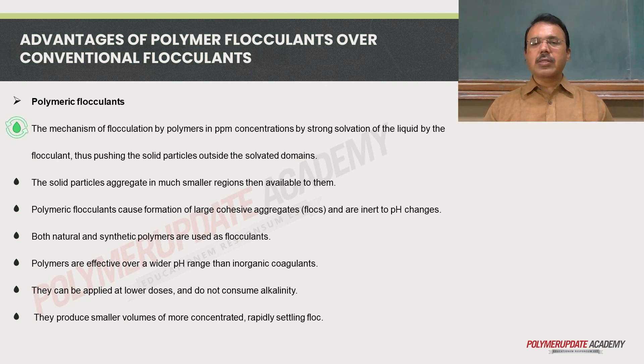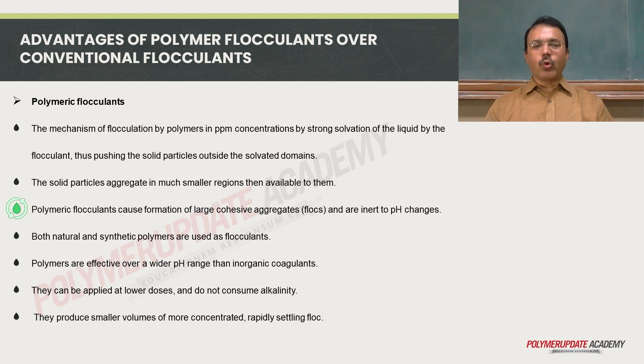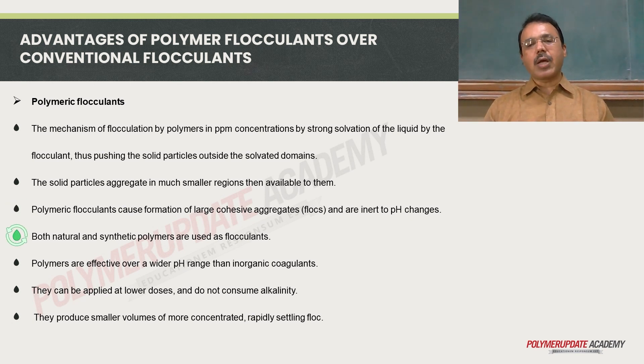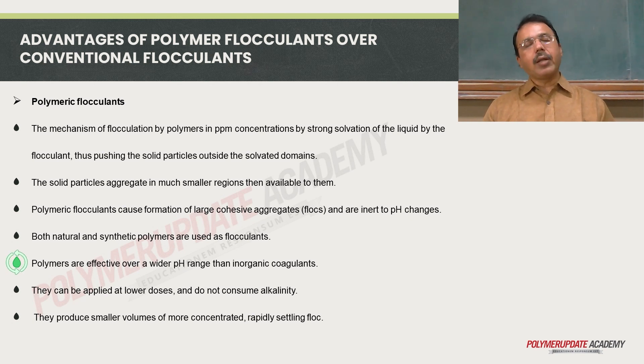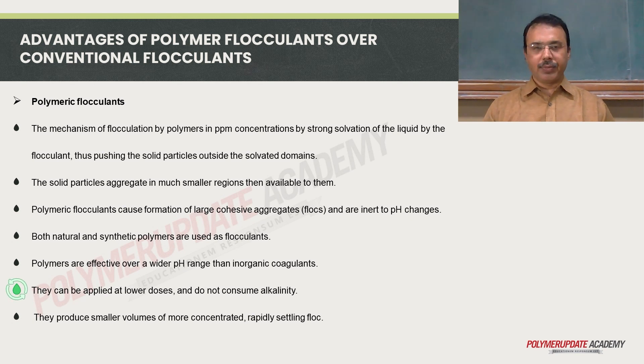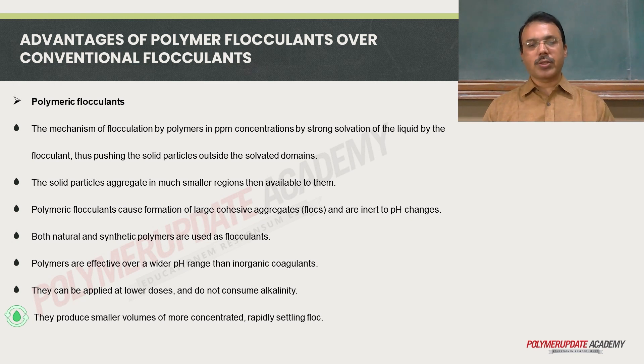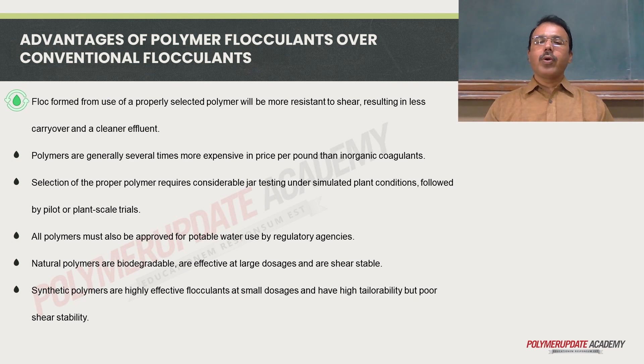This solvation pushes the solid particles outside the solvated domains. The solid particles then aggregate in much smaller regions than otherwise available to them. Polymeric flocculants cause formation of large cohesive aggregates or flocs and are inert to pH changes. Both natural and synthetic polymers are used as flocculants. Polymers are effective over a wider range of pH than inorganic coagulants, can be applied at lower dosage, do not consume the alkalinity of water, and produce smaller volumes of more concentrated, rapidly settling flocs.